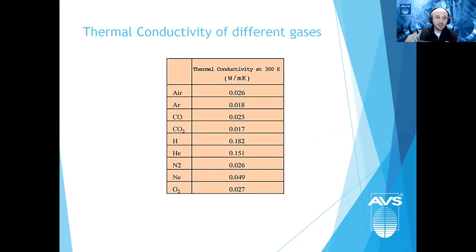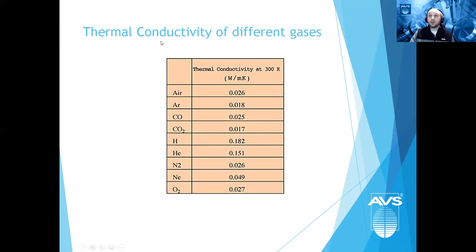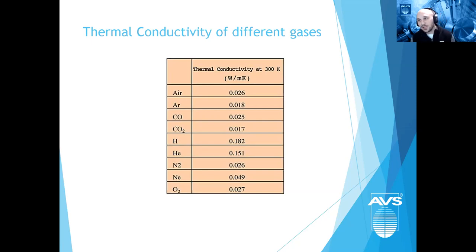Because different gases have different thermal conductivities, gas-dependent gauges calibrated in nitrogen will give skewed readings for other gases. Standard gases like nitrogen, air, carbon monoxide, or oxygen are reasonably close, but other gases will throw off the measurement and must be accounted for.